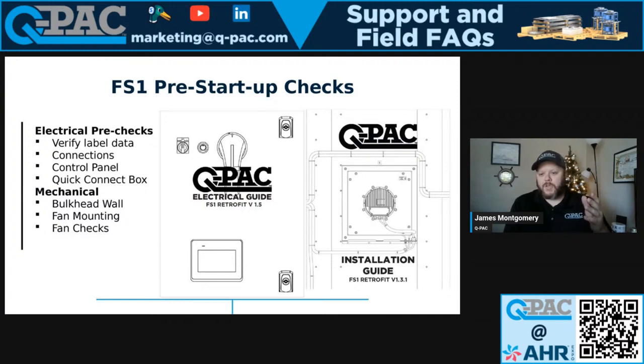I say control voltage, that's a misnomer. We're going to talk about scope gaps in just a second, but it's actually low voltage. We call it control, but you may not refer to it on the site as controls because typically your controls is done by a controls contractor. This is actually low voltage and needs to be run in a separate conduit than your high voltage.